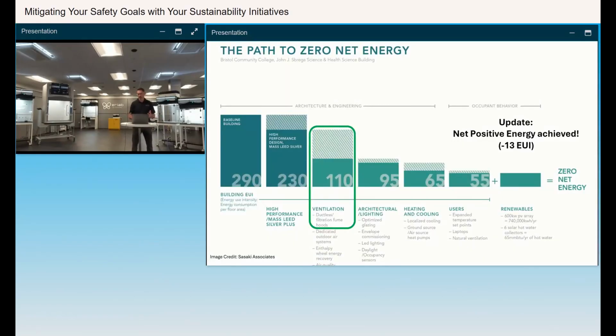So on their path to zero net energy, if you look at the energy use intensity, the original high performance design was at 230 EUI. The biggest reduction was in the ventilation category, which the ductless fume hood played a significant part. They were able to reduce it by 120 EUI.